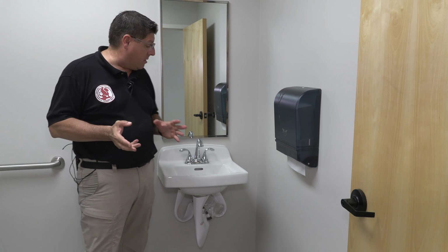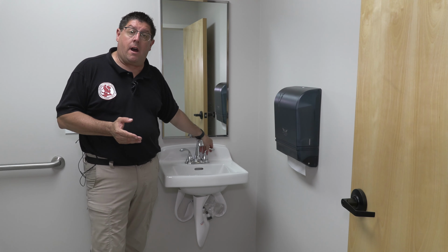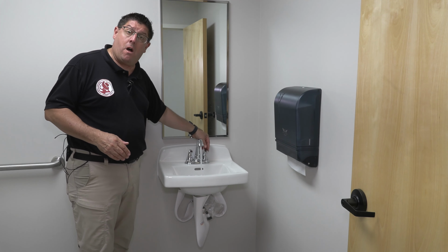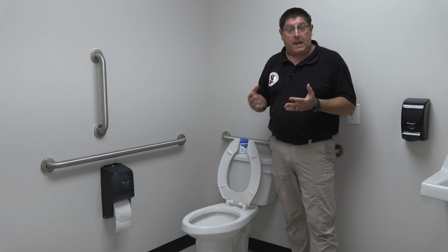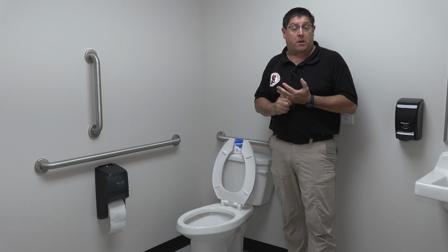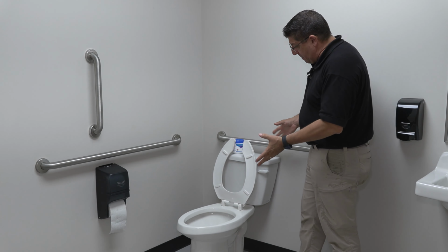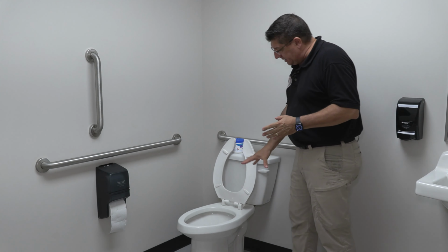But part of the standard, though, we do want to double check and make sure, again, cold is on the right side, hot is on the left side, and we have got functional flow through both systems. When inspecting the commode, again, we need to flush a representative sample of the commodes. And then we need to make sure that they're tight to the floor and the basins are free of cracks, including the tank lid, the side of the basin.